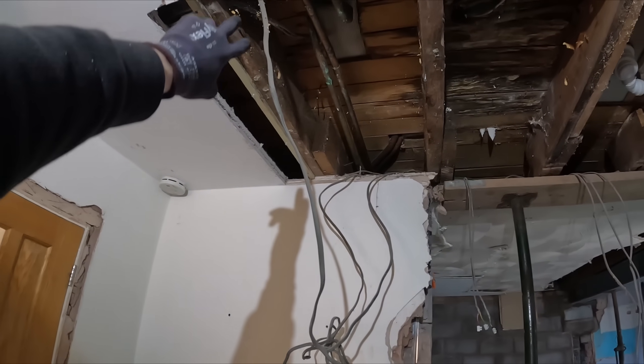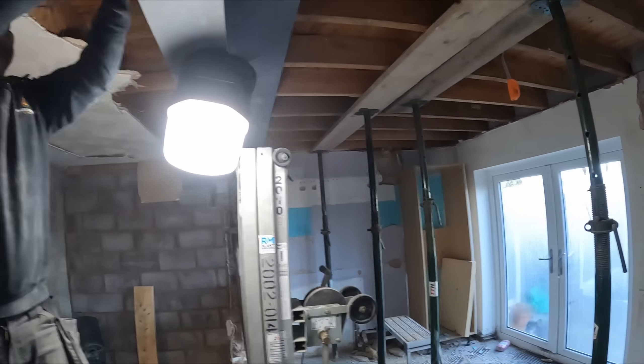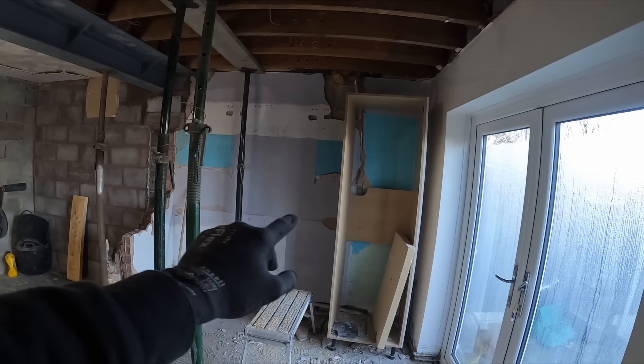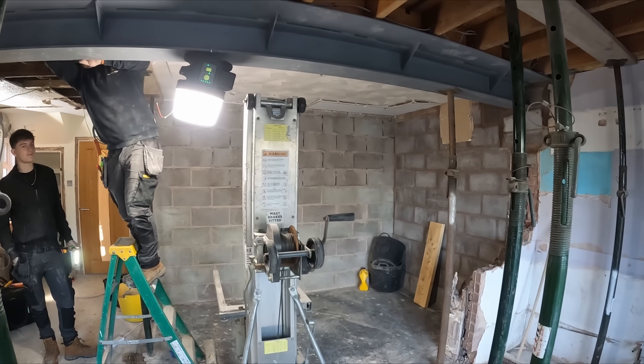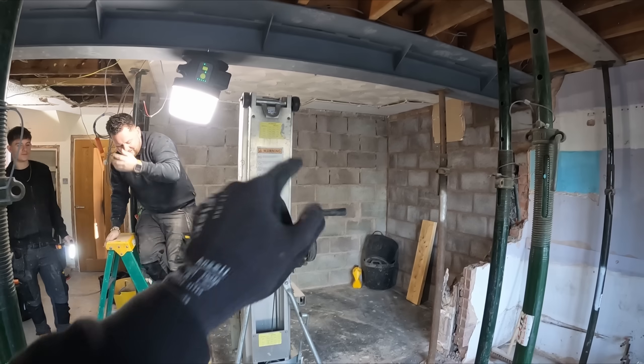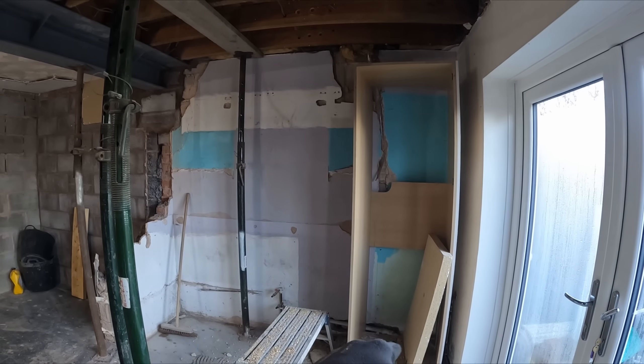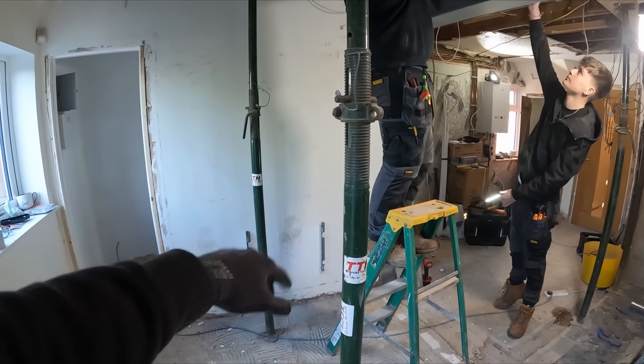We've got an old fuse board in there that's all getting updated. I've just drilled two 28mm holes all the way through these joists. Got the new uni light, little UFO light hanging off the RSJ, being an absolute beast. We've got a kitchen - fridge, freezer, dishwasher, all sorts of appliances. Then we've got loads of tall units. We've got a cooker and a hob. So we're running new six mil, three radials - a radial for the appliances, a radial for worktop sockets, and then a utility going here as they're extending the stud wall.